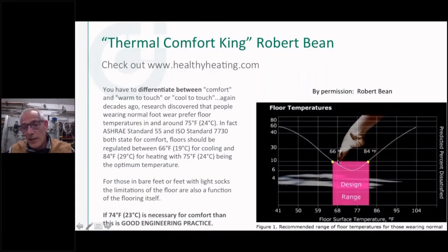And he's shown this design temperature here in this range. In fact, I think this article, one of these standards over here, ASHRAE standard 55, suggests 75 degrees being an optimum temperature. I tend to think, for me anyways, that's a little on the cool side. If I stepped on a 75 degree slab, while it might be covering the heat load, it might not feel warm to your customer's feet. So if they're expecting a warm slab all the time, that's probably getting a little bit low. So usually somewhere around that 82 degrees seems to be about right for me, surface temperature.